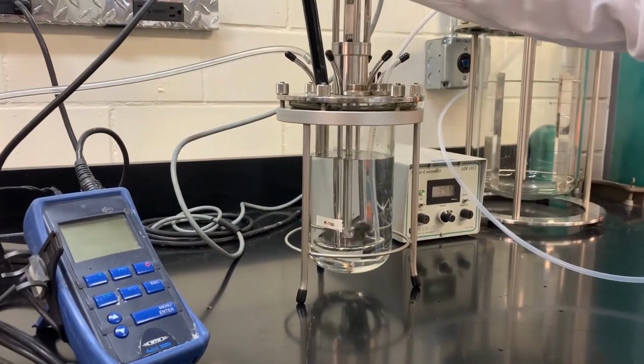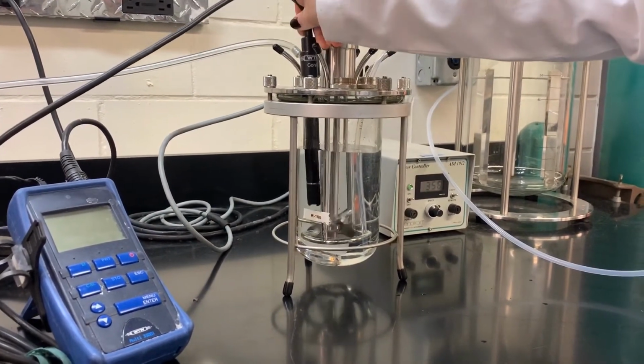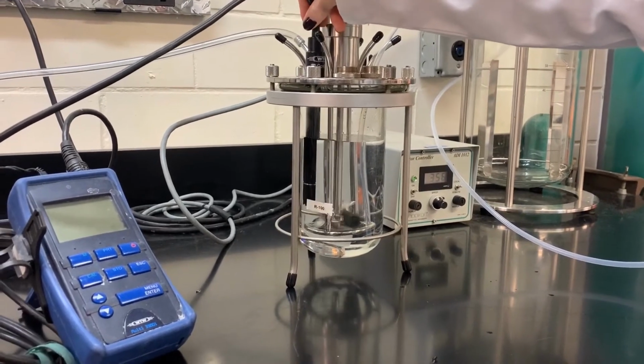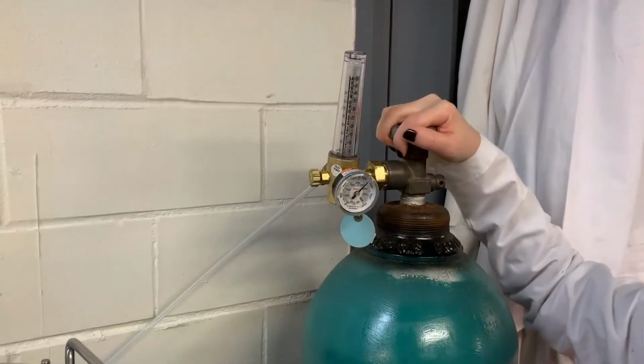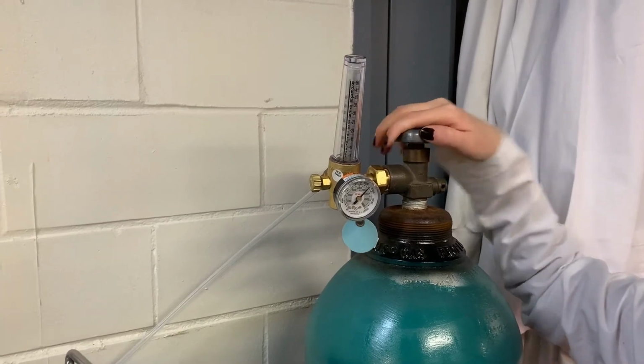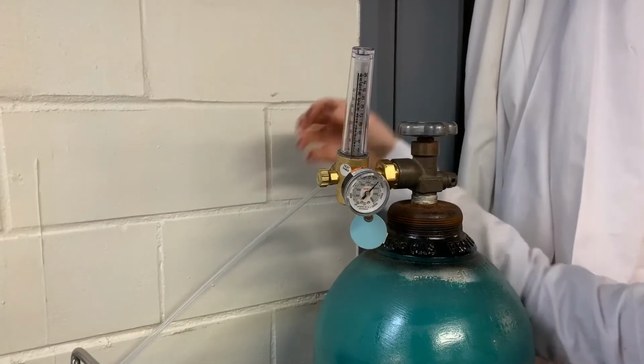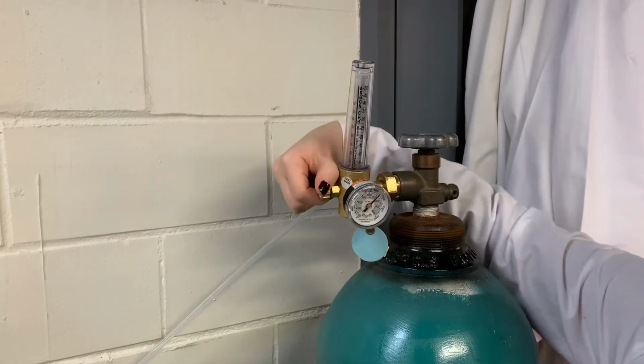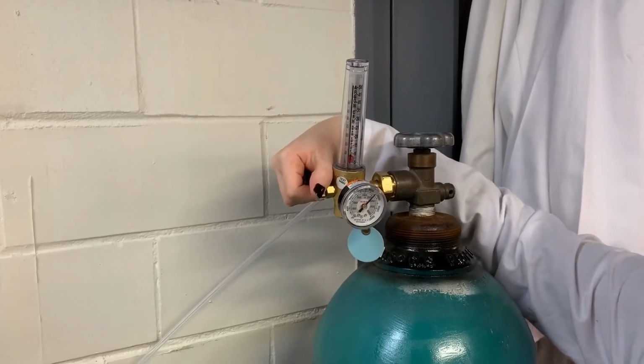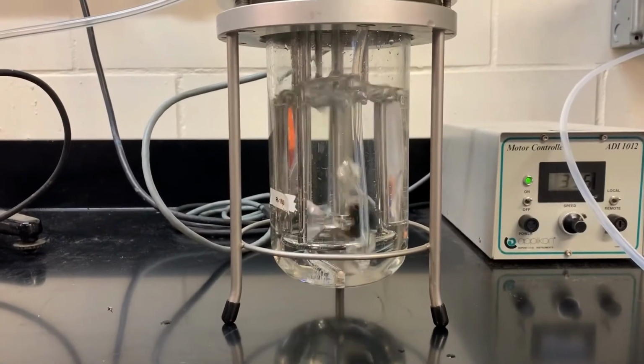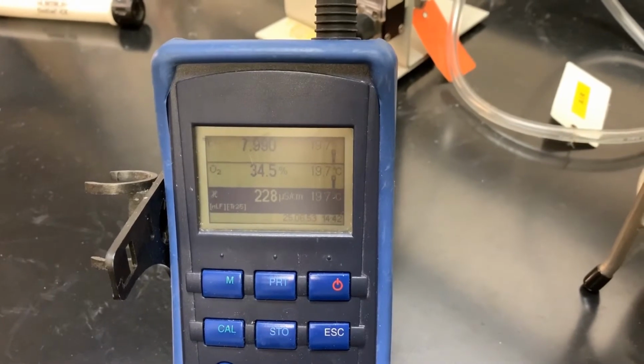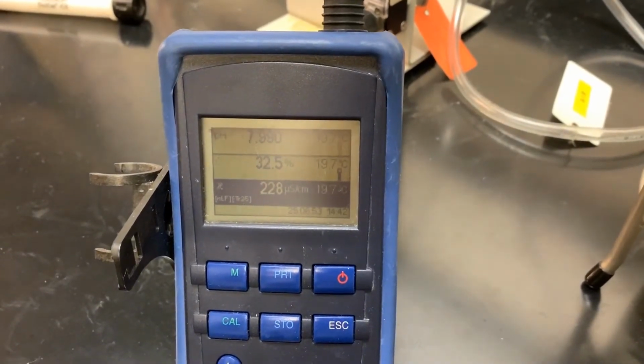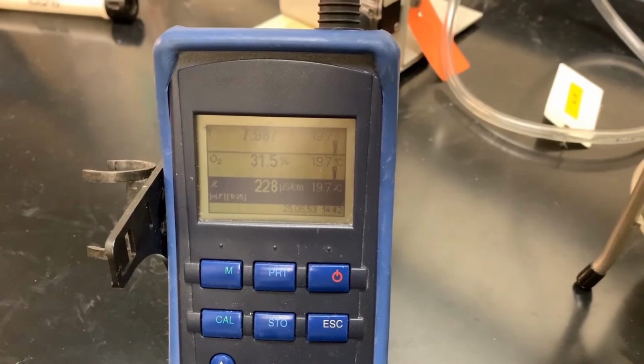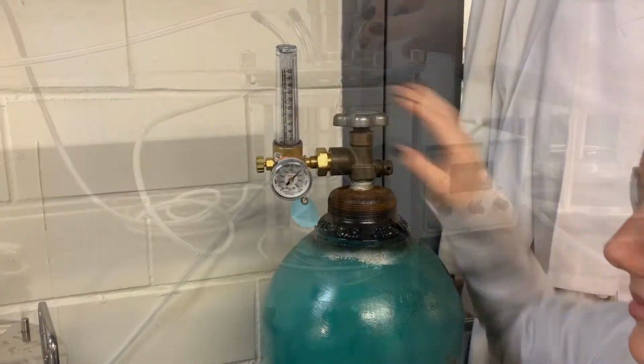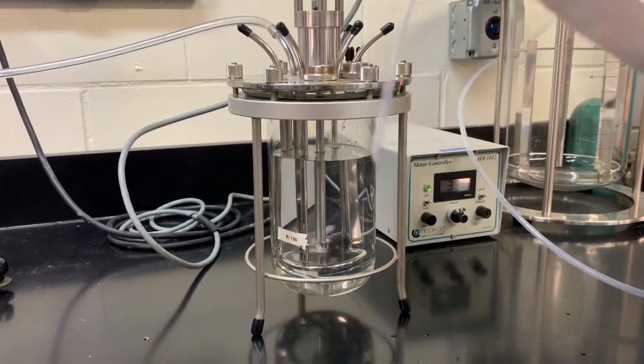The DO probe should have been previously calibrated. If it appears the probe is not calibrated, notify a lab instructor. To begin the flow of nitrogen into the bioreactor, open the valve at the top of the nitrogen tank, V2, about a quarter turn. Then, slowly open the flow indicator valve until bubbles appear in the bioreactor vessel. Be sure not to open the valve too much, as it will cause excessive bubbling and could lead to a spill. Continue to sparge with nitrogen until the DO probe value reaches approximately 0% oxygen. Close valve V2 and remove the nitrogen line.